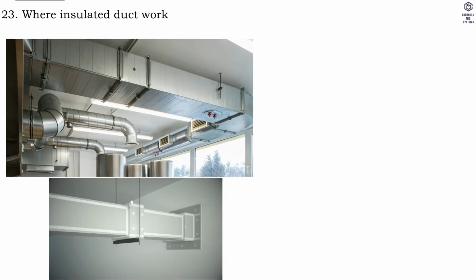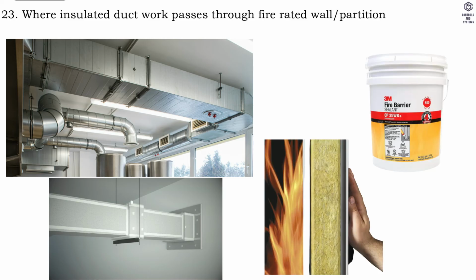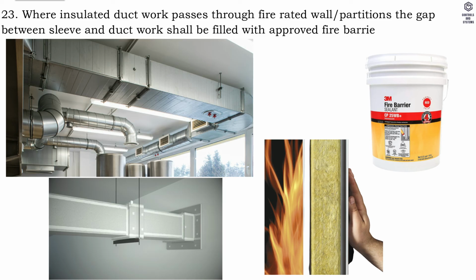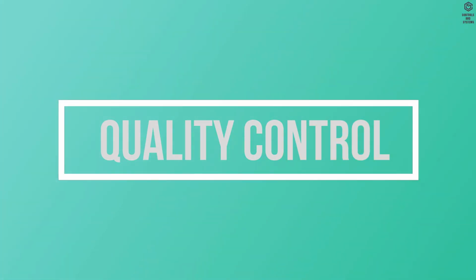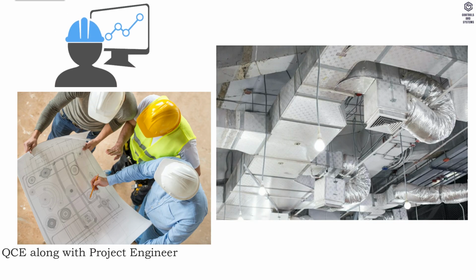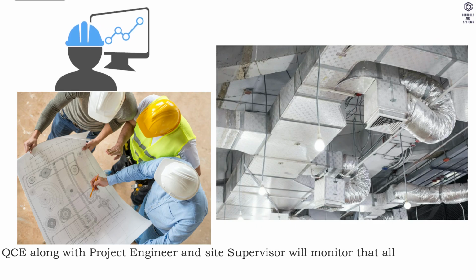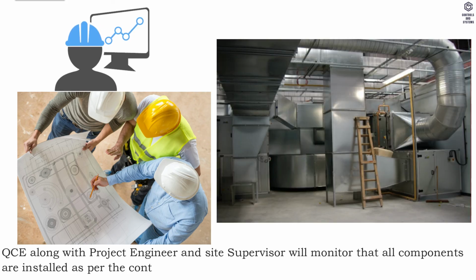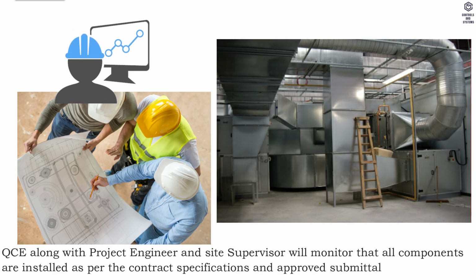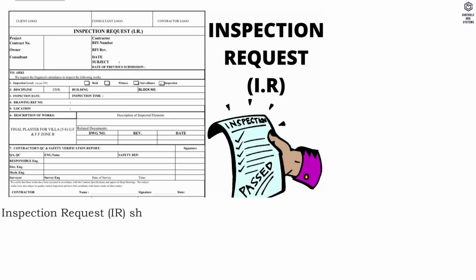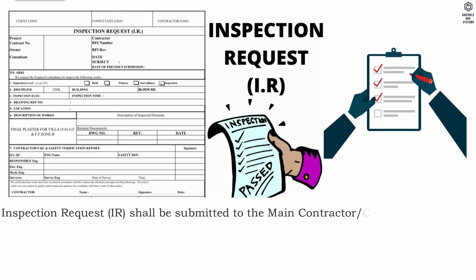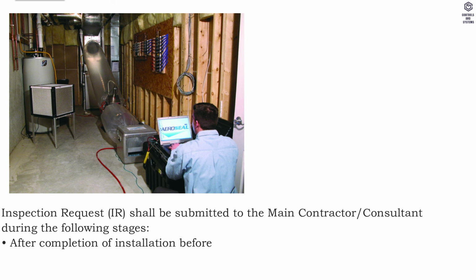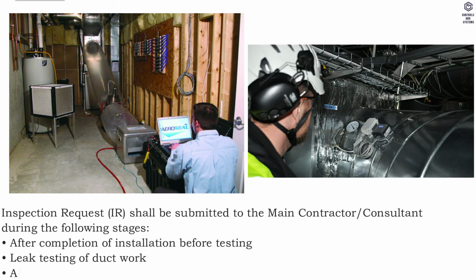23. Where insulated ductwork passes through fire-rated walls and partitions, the gap between sleeve and ductwork shall be filled with approved fire barrier. Quality control. QC engineer along with project engineer and site supervisor will monitor that all components are installed as per the contract specifications and approved submittals. Inspection request, IR, shall be submitted to the main contractor and consultant during the following stages: after completion of installation, before testing, leak testing of ductwork, and after complete installation.